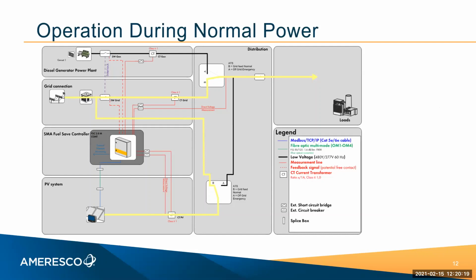After the solar connection, there would be sort of where it says SW grid. That would show where the meter would be for the utility. And then the power starts through a second ATS and then off to the loads of the building, which is in the top right. The third box down the left that says SMA fuel save controller, that's the box Jackson was just showing. It's connected to the PV.